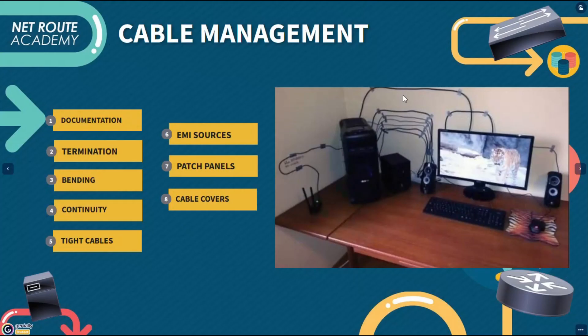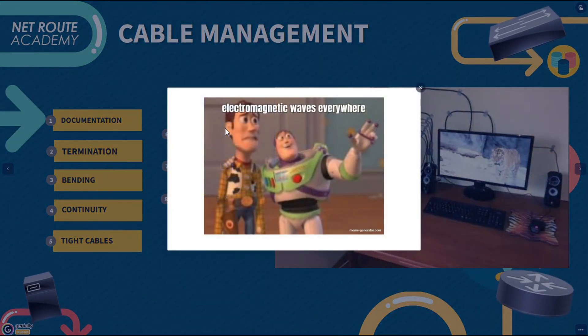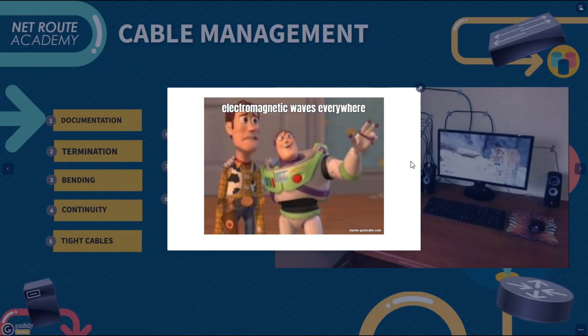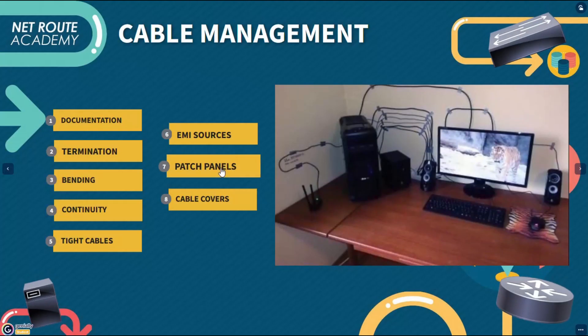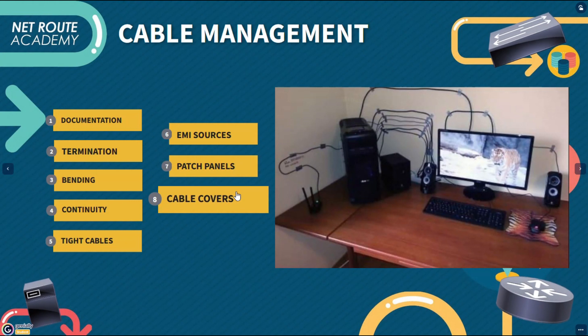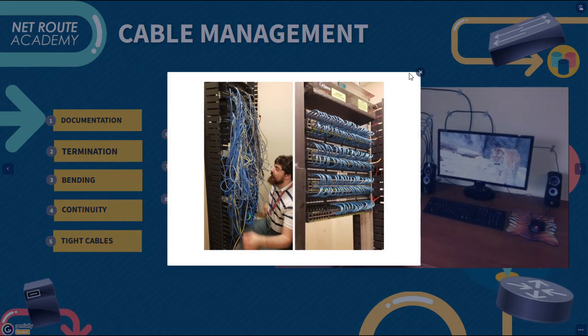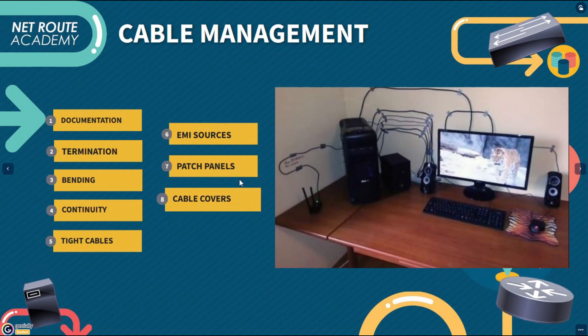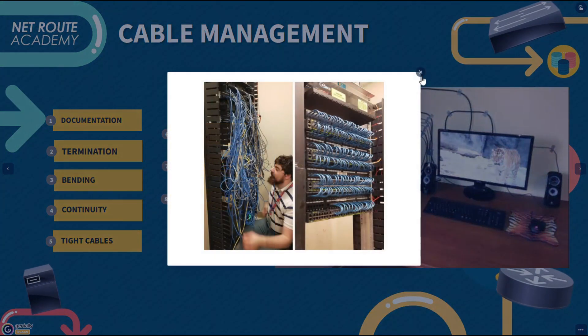Next is electromagnetic interference or EMI sources — make sure installed cables are at least three feet away from fluorescent lights or any EMI sources, such as power lines, televisions, copiers, or anything with electrical activity. Finally, use patch panels to organize and connect lines, and use cable trays for cable management to secure your cables in place.